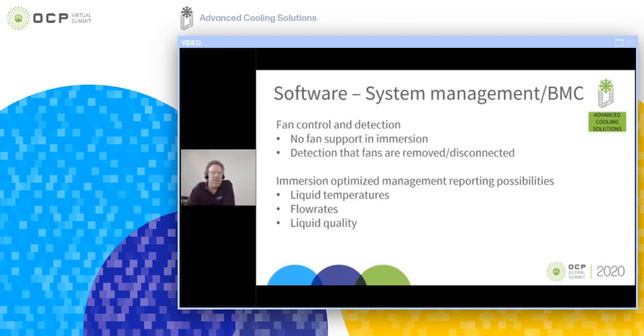Next thing to consider is the system management capabilities, or the BMC. Fan control and detection is something that is widely known to be a factor for immersion. So fan support in immersion should be disabled. Or the fan detection and fan safety mechanisms should all be disabled when you're dealing with a server that is immersed in liquid. Usually, most vendors or most integrators will remove fans to promote liquid flow further, and that detection should be disabled.